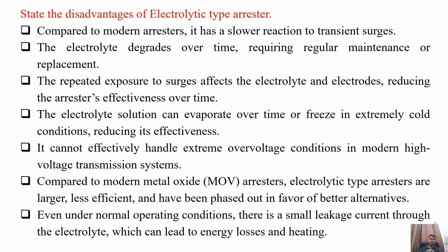State the disadvantages of the electrolytic type arrestor. So, there are several disadvantages as these were some ancient type of arrestor which were used in early days. Compared to the modern arrestors, it has a slower reaction to transient surges. The electrolyte degrades over time, requiring regular maintenance or replacement. The repeated exposure to surges affects the electrolyte and electrodes, reducing the arrestor's effectiveness over time. This electrolyte solution can evaporate over time or freeze in extremely cold conditions, reducing its effectiveness, and the operation of the arrestor is at stake.